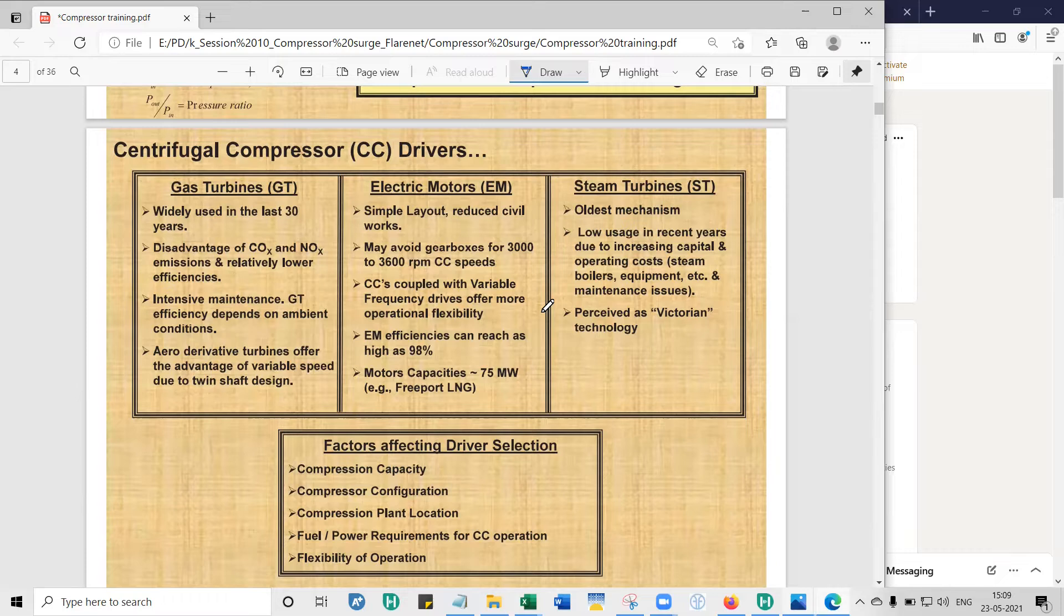The advantage with electric motors, you don't have to bother about steam or natural gas. You just need electricity. The layout is simple. You don't have, like a gas turbine, you don't have to worry about lube oil leaking. The amount of lube oil that you need, lube oil and sealing with dry gas seals, you don't have those problems with electric motors. All it needs is power. The advantage with electric motors over the other two kinds of drivers is that you've got very high efficiencies. You can hit as high as 98% efficiency.